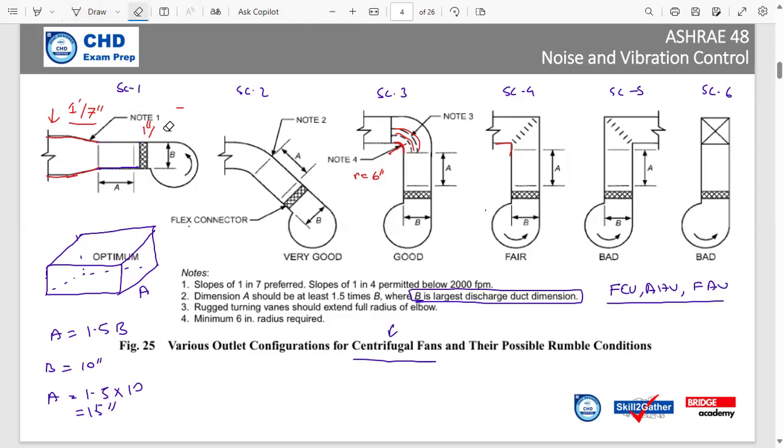However, in many cases, I have seen mistakes. There are common mistakes. What I see in my observation is like this. The engineer or designer, at the connection here, has the flexible duct, and suddenly, without getting into this horizontal direction straight, they make it larger.